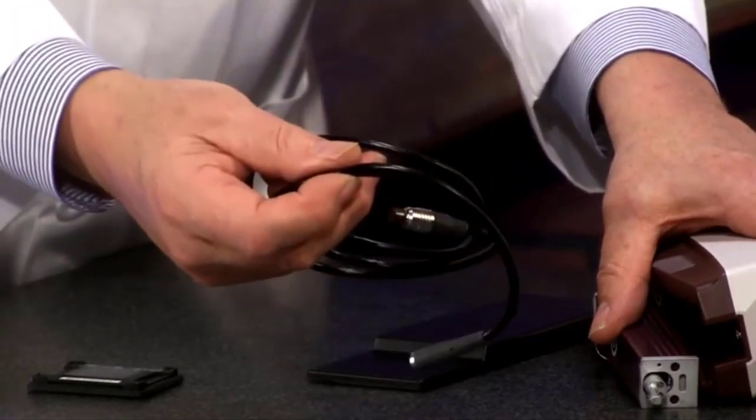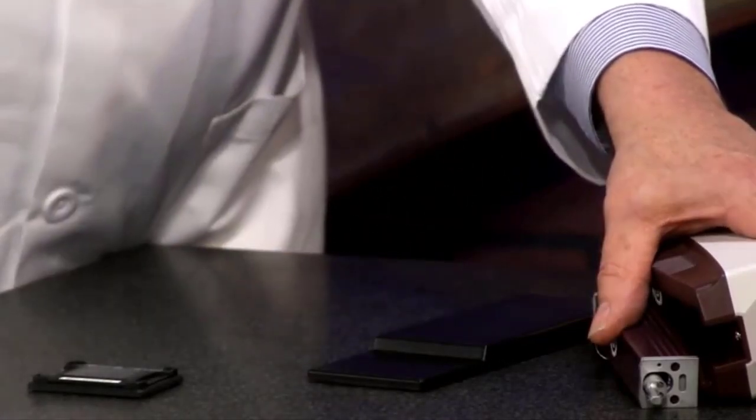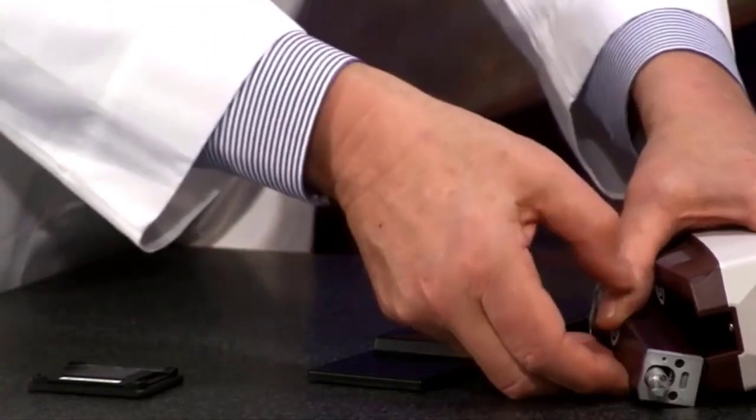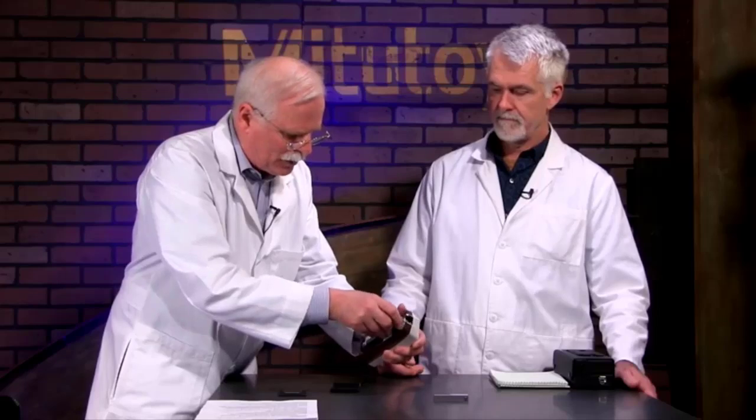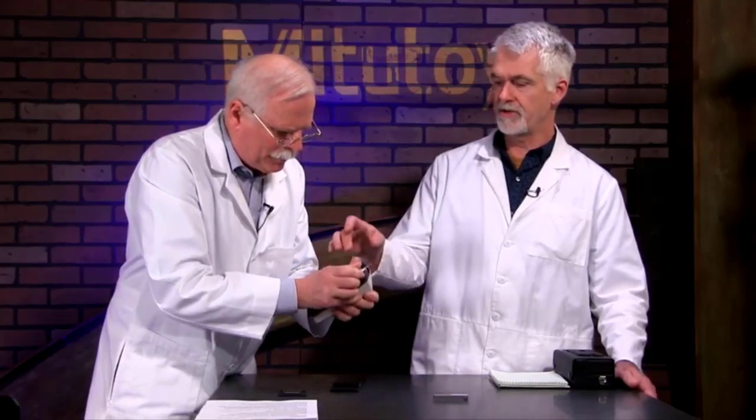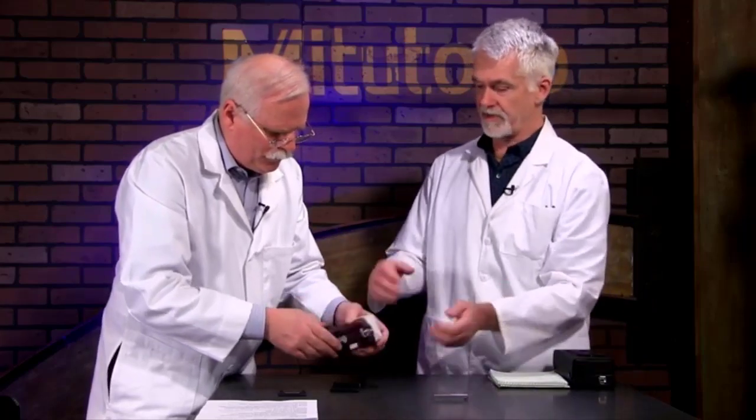The drive unit itself you can separate from the case, and they have a connecting cable so you can get out about 3 feet away in case the probe has to take a measurement somewhere and your display just won't fit. You can do it that way. So let's put this all back together again. You just detach the drive unit as you show, and you can put that somewhere else from the display. It can be in a safe place, maybe where no coolant's pouring on it, that sort of thing.